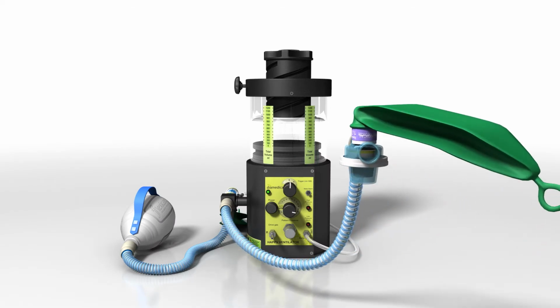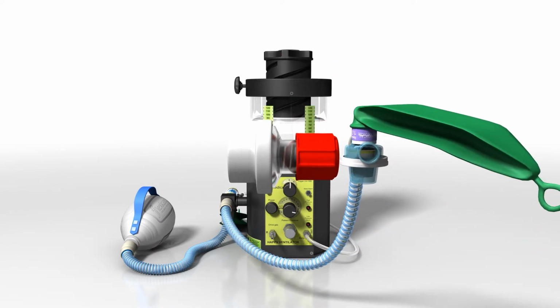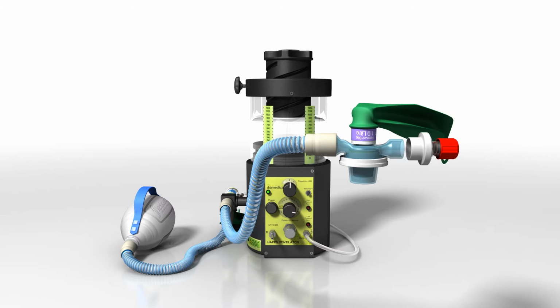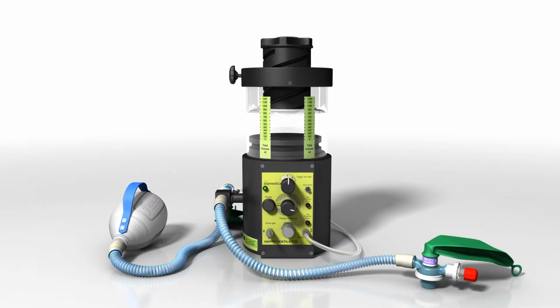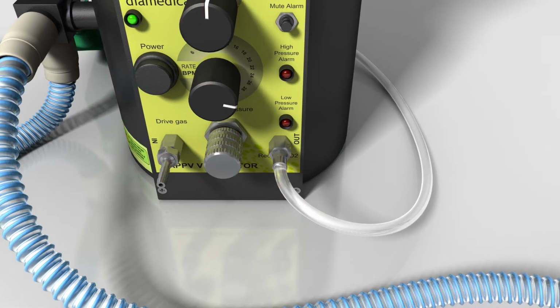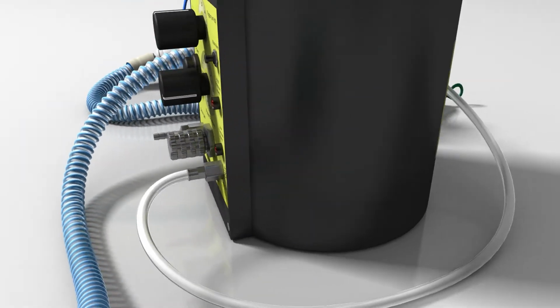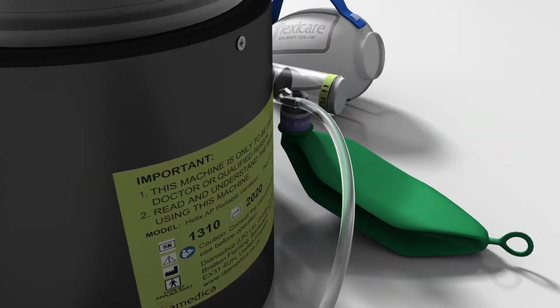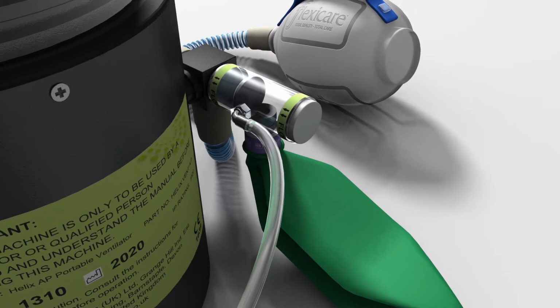Expired gases leave the patient valve, which can have PEEP applied at this point, 0 to 20 centimeters water pressure. The gas used to drive the ventilator is recycled to ensure there is no waste of oxygen and is put back into the inspiratory valve via the recycled tube.